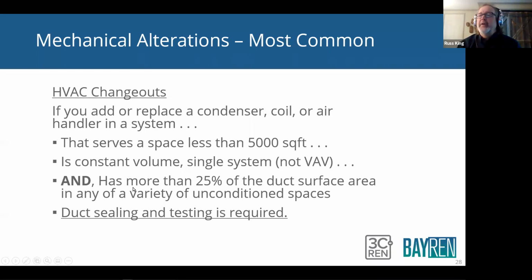So here's kind of how it works. If you add or replace a condenser, coil, or air handler, which a package unit is all of those things, that serves a space less than 5,000 square feet, not a building, but a space, and it's constant volume, a single system, which means not VAV, and has more than 25% of the ducts in any variety of unconditioned space, such as attic or up on the roof, duct sealing is required. So if you meet these requirements, duct sealing is required, and testing by a third party, all right? So be aware of that.